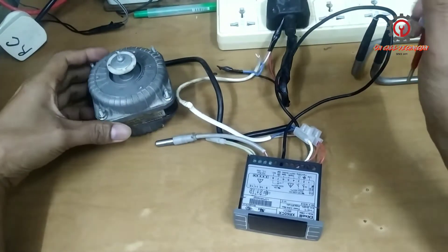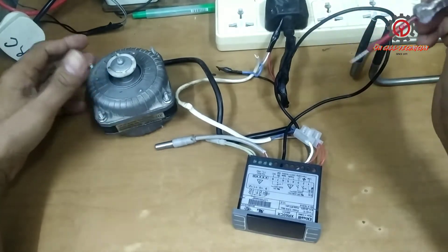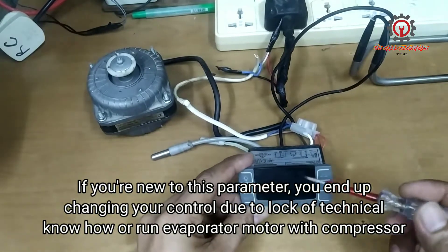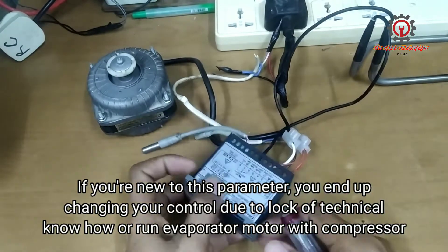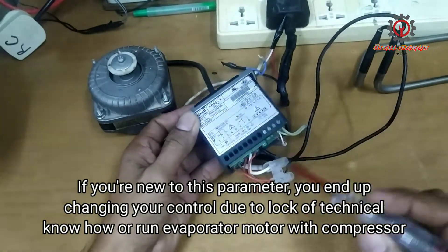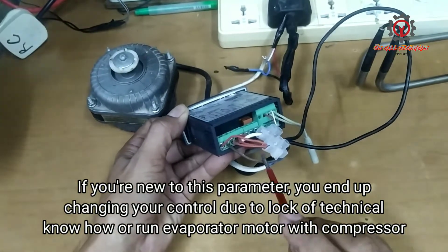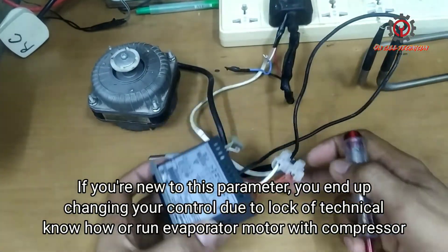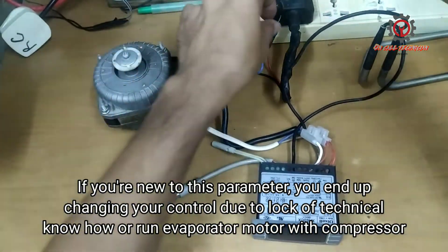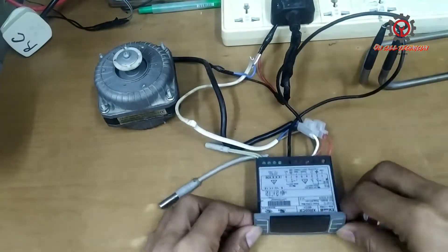Welcome once again guys to my YouTube channel. Today I'm going to teach you how to fix FST — Fan Stop Temperature — of the Dixell XR60CX. The load here is for the fan motor. I'm going to show you that the FST default is two degrees Celsius. Let's power this on.